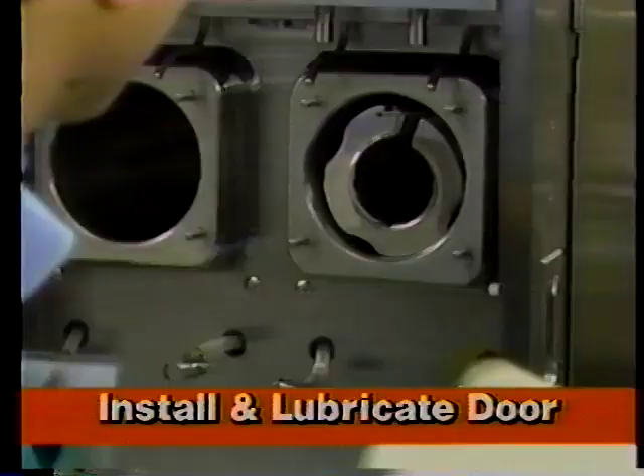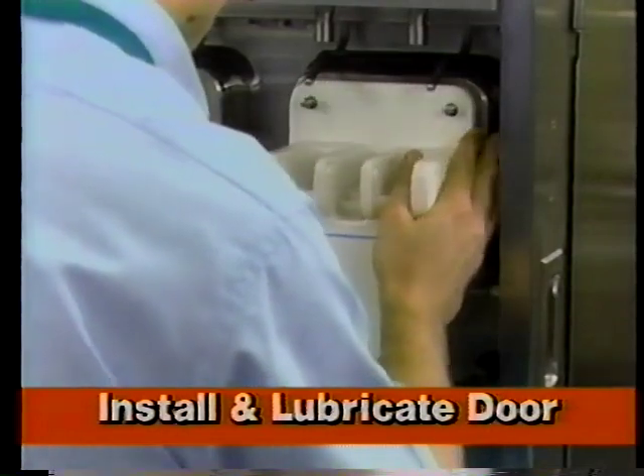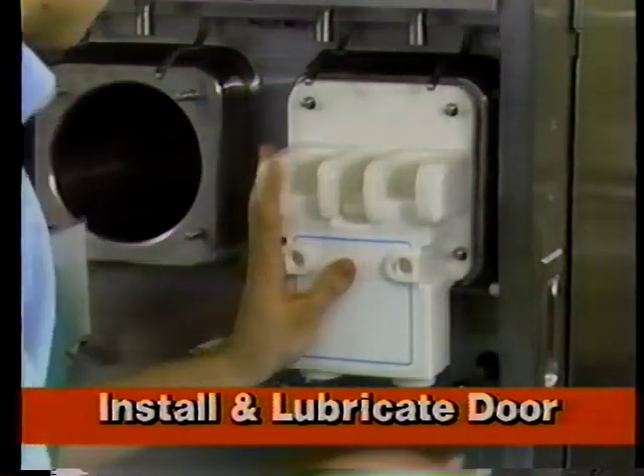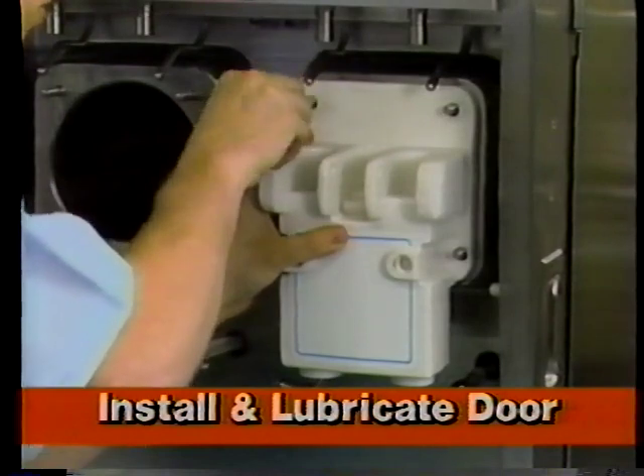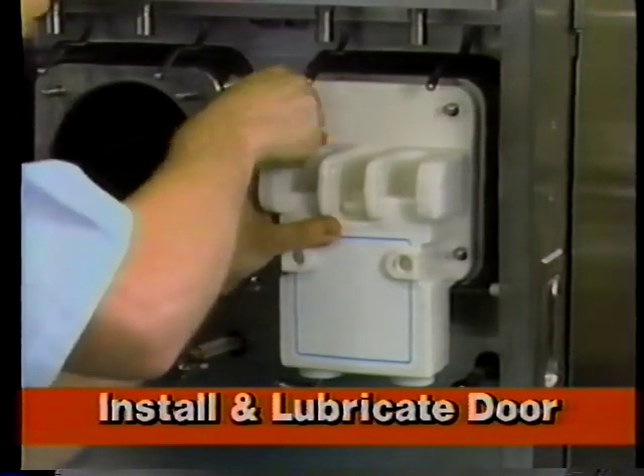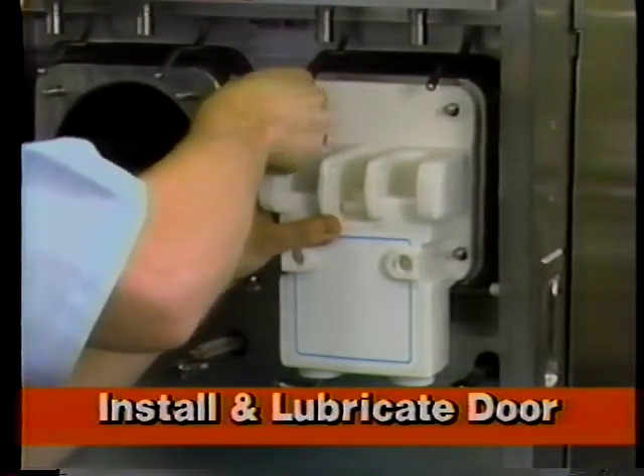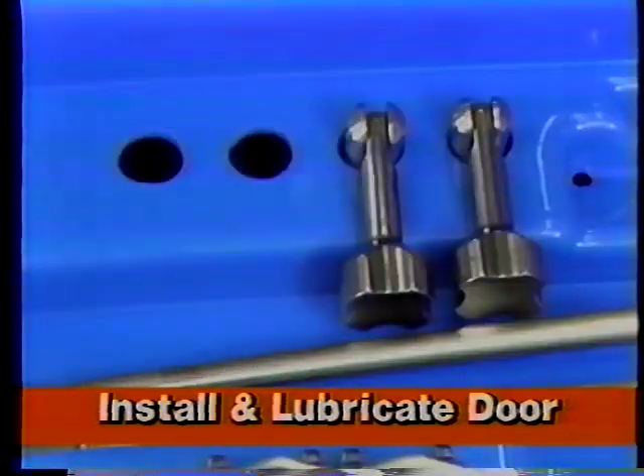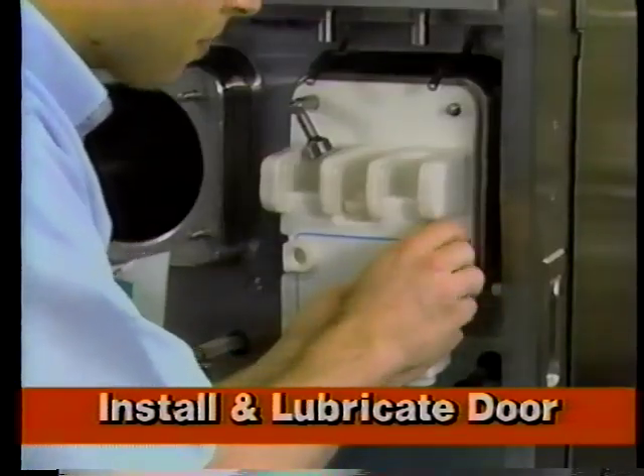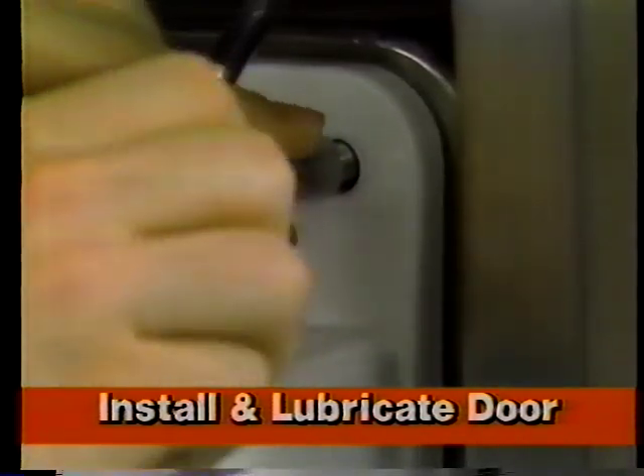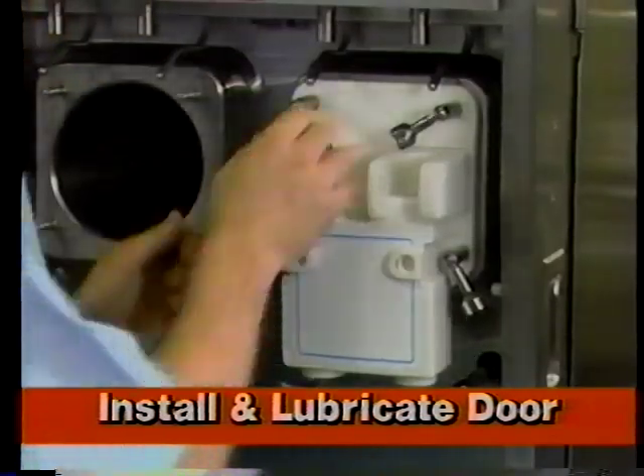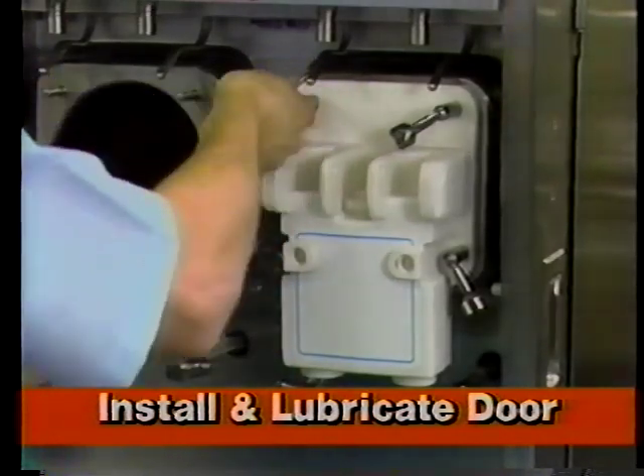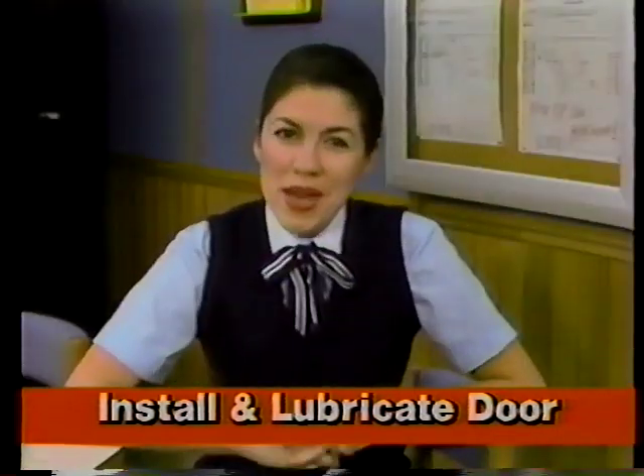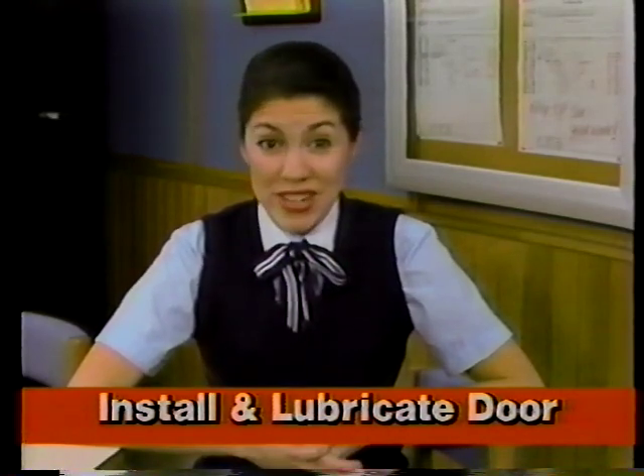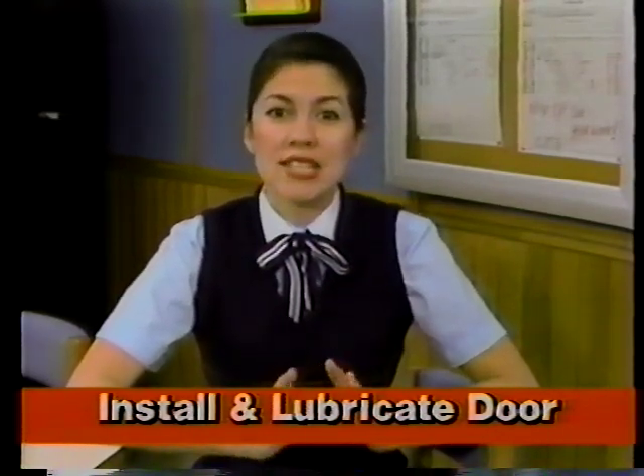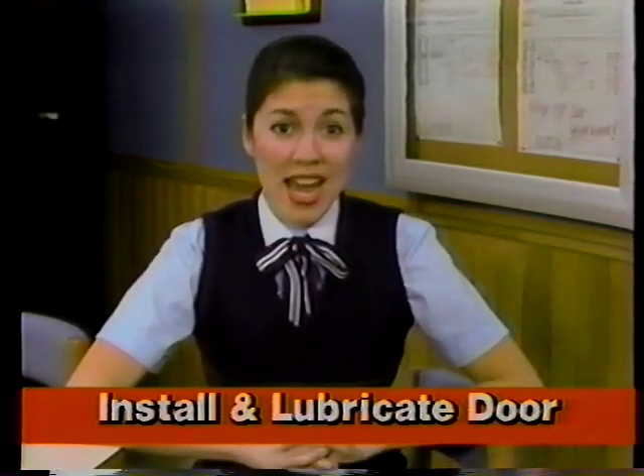The door fits over the 4 studs on the front of the freezing cylinder, and it's held in place by 4 hand screws. Put the screws on in a crisscross pattern. First this screw, then this one, then over here, and the last one. And then go back and tighten them down the same way. That's the best way to get the door on tight and even. Just get the hand screws nice and snug. Never use force to tighten them.